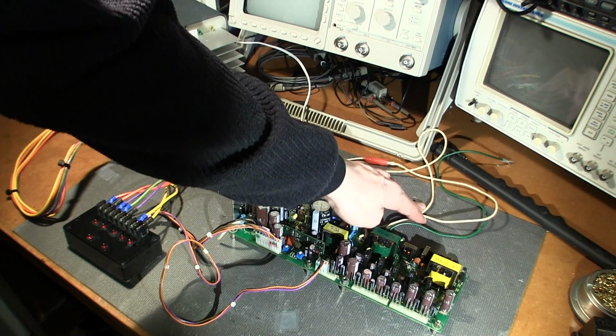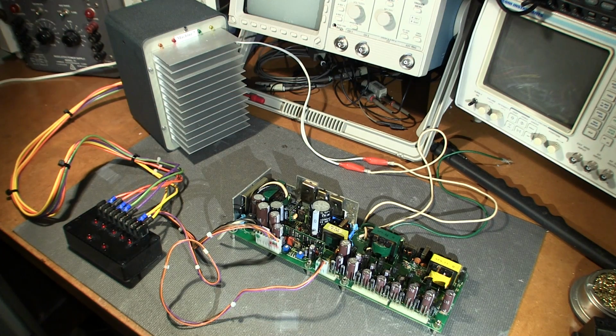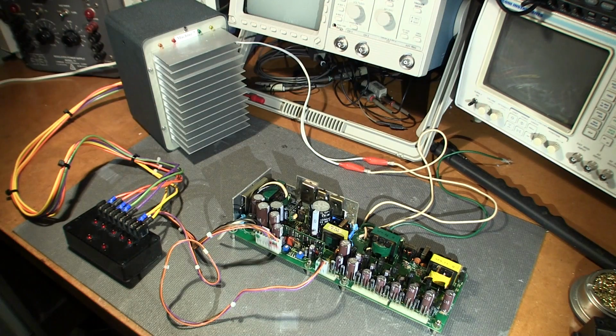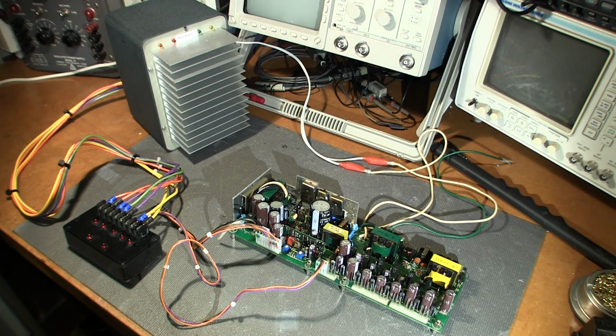These two wires here are connected to my variac and isolation transformer supply so that I can give this power supply 200 volts, which is what it needs in order to operate. Keep in mind that whenever you're testing a power supply like this, you should always have an isolation transformer just to keep yourself a little bit more safe. There's a lot of things involved in the safety aspect of working on stuff like this that involves high voltage. So again, if you're following along, you're doing so at your own risk.